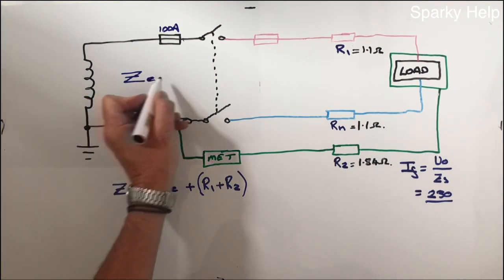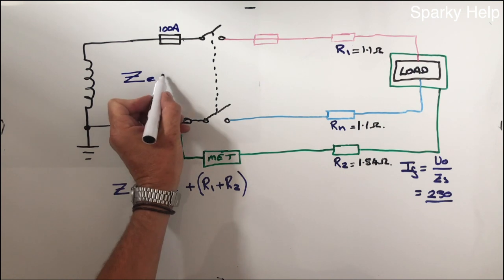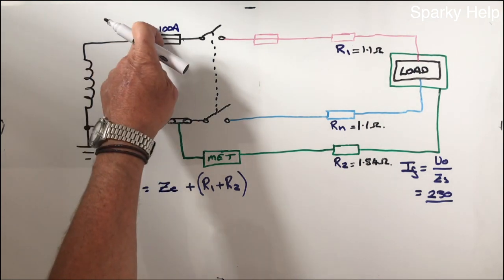Let's give ZE a value, because it's a TNCS, the maximum value would be 0.35 for 100A supply.